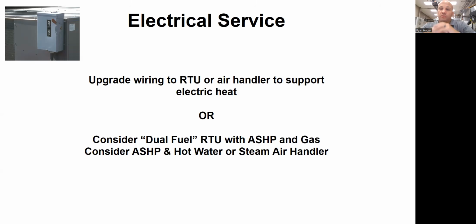So I can have a dual fuel split system with the outdoor unit being a heat pump and the indoor side having a hot water coil connected to a gas-fired boiler. And then I could do the math like we were doing a little bit earlier to figure out what that changeover point is, when I want to use the boilers to heat the building and when I want to use the heat pumps to heat the building. And it's not a big cost. I'm paying whatever the price difference is between an AC and the heat pump version of the exact same piece of equipment. And I'm paying for a little bit extra thermostat wiring. And I could have a dual fuel heat pump system with a hot water or steam air handler.